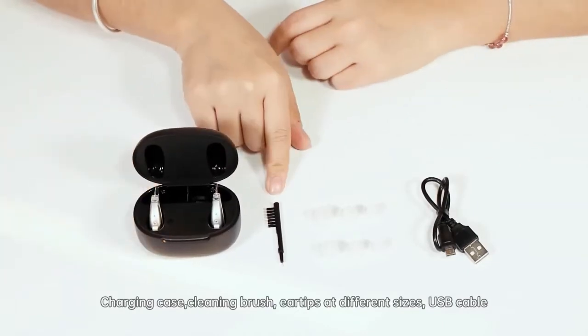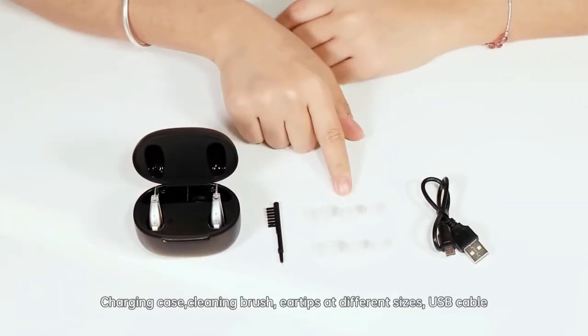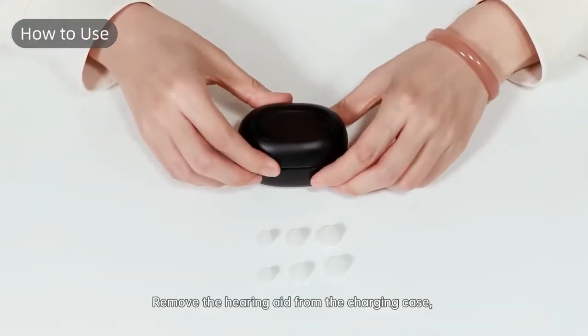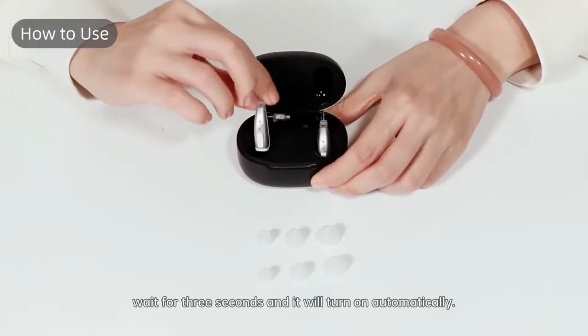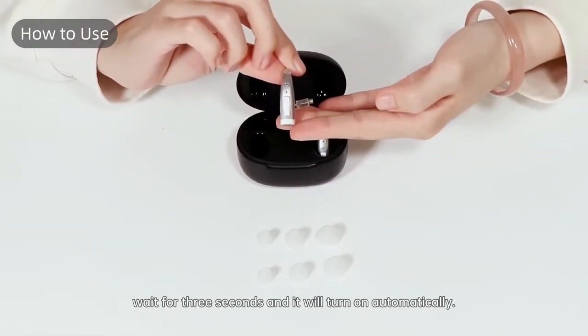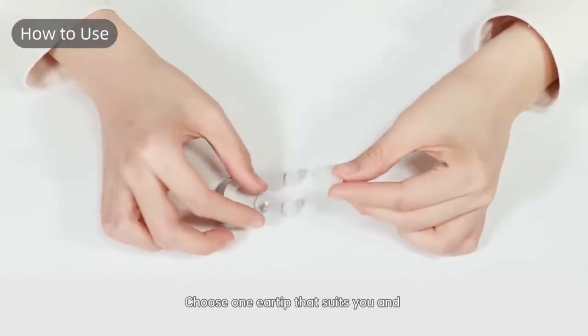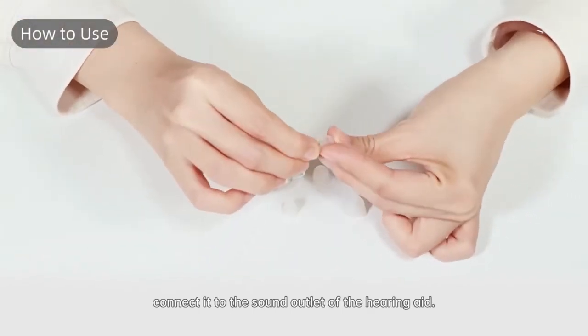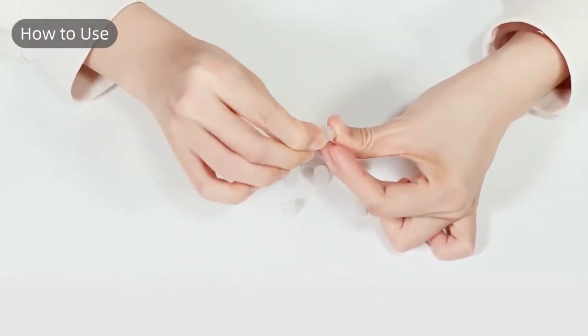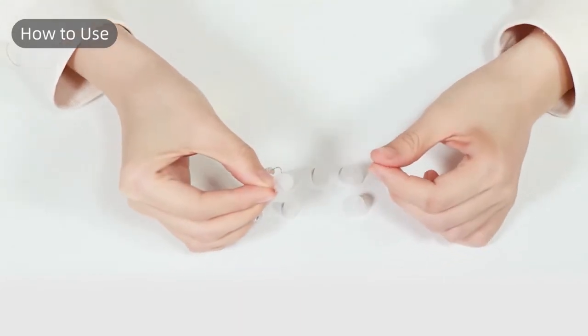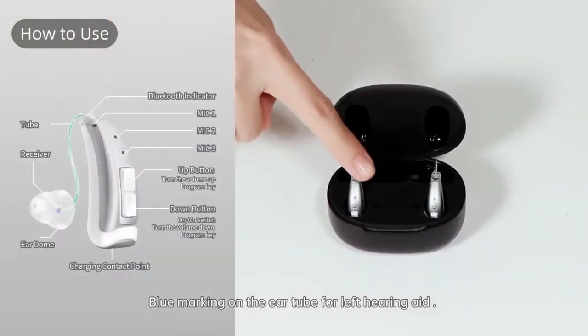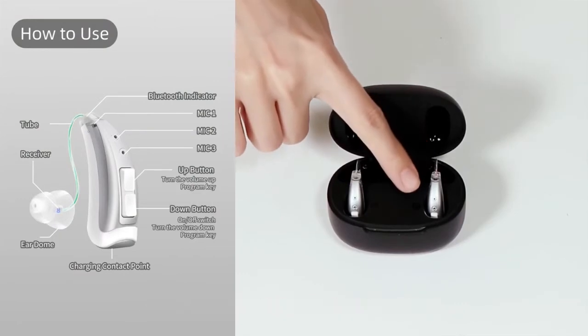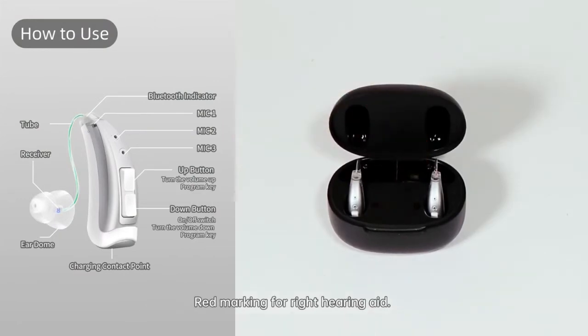Charging case, cleaning brush, ear tips of different sizes, and USB cable. Remove the hearing aids from the charging case. Wait for 3 seconds and it'll turn on automatically. Choose one ear tip that suits you and connect it to the sound outlet of the hearing aid. Blue marking on the ear tube for left hearing aid, red marking for the right hearing aid.